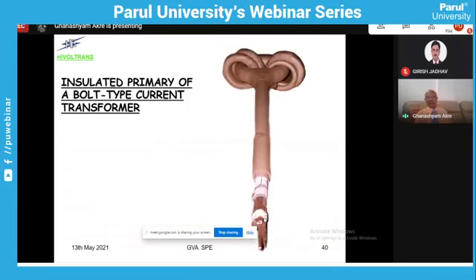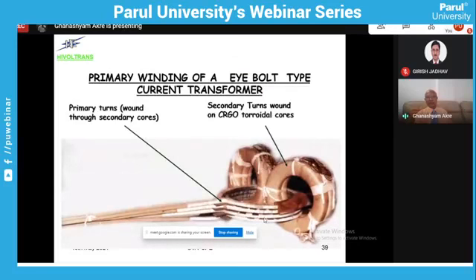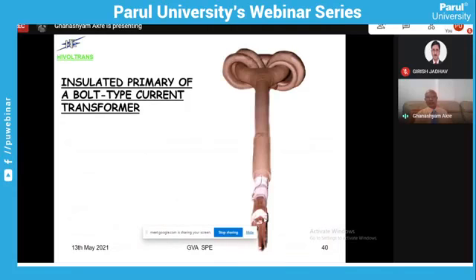The shape of the transformer is a bolt type, which I have shown here. Now, when it is assembled and ready for the insulation, it will occupy this type of shape. You see, the primary, which was in rectangular sections, is now completely rounded off. And the leads are also taken out in a round tube, because if insulation is provided on the rectangular strip, it will create sharp corners at high voltage and they will fail, because sharp corners will always produce partial discharges in the region occupied by the insulation.